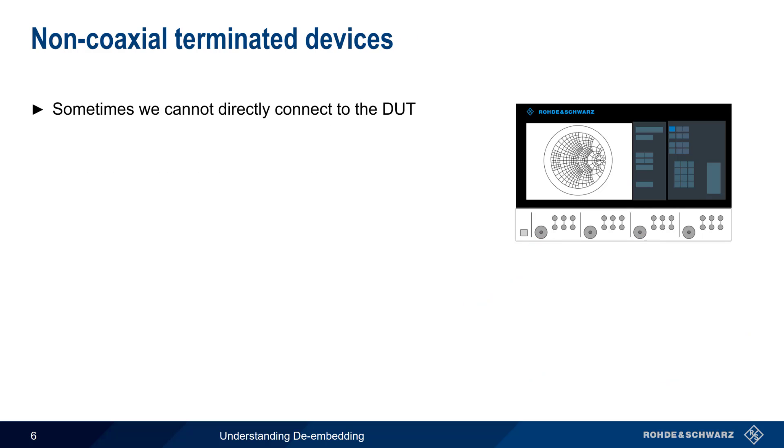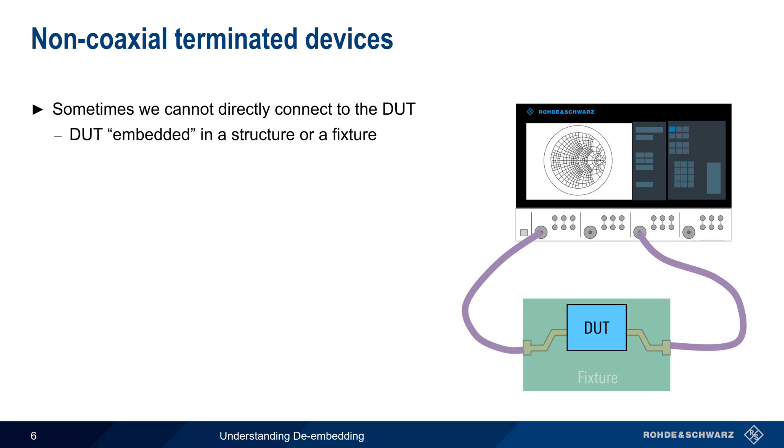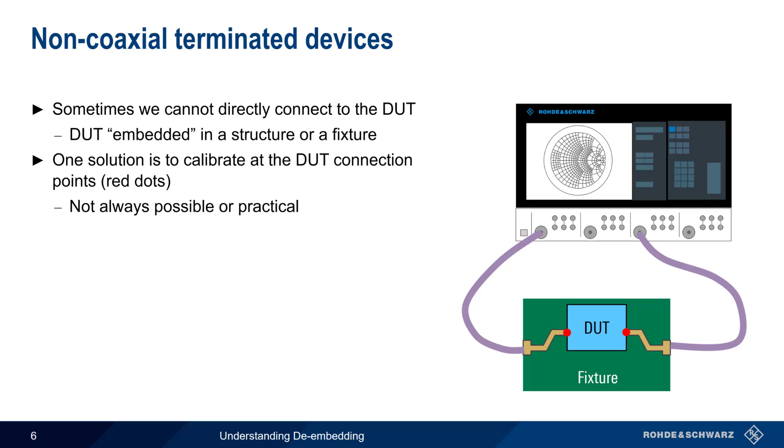So, what do we do if we can't directly connect our VNA to the DUT? For example, when our DUT is embedded in a structure or a fixture? One solution would be to somehow calibrate at the connection point between the DUT and the fixture, shown here as red dots. But this is not always possible or practical. There are, however, various methods that can be used to remove the effects of the fixture, and this is sometimes referred to as fixture compensation.